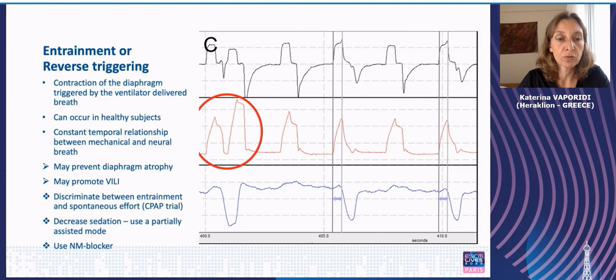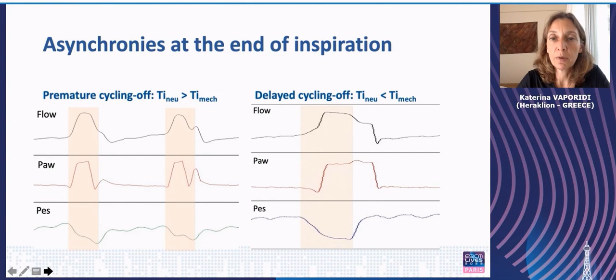Moving on to asynchronies occurring towards the end of inspiration. These asynchronies occur with modes where the neural TI is not the sole determinant of the mechanical TI. This occurs in all conventional modes of assist: volume and pressure assist control, SIMV, and also pressure support. It does not happen with proportional modes. When the neural inspiratory time is longer than the mechanical, we talk about premature cycling off, while when the neural inspiratory time is shorter than the mechanical one, we talk about delayed cycling off.